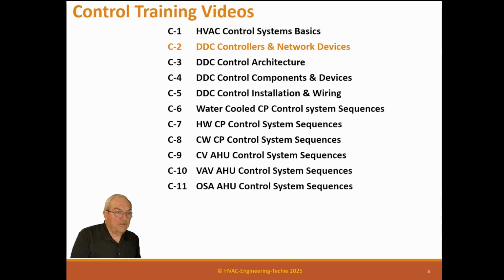This wheel has been developed by different control manufacturers, and they do work well. My goal as a commissioner was always to get them to use a factory sequence or a well-developed sequence that works every time, instead of going through the process of inventing a new sequence, trying to program it, and failing 100 times before you figure out how to make it halfway work. It's much easier to use these.